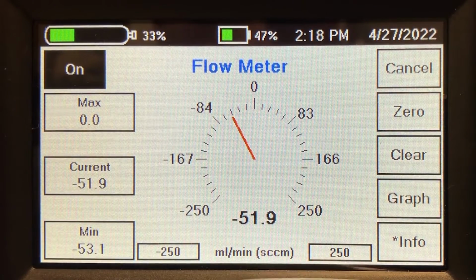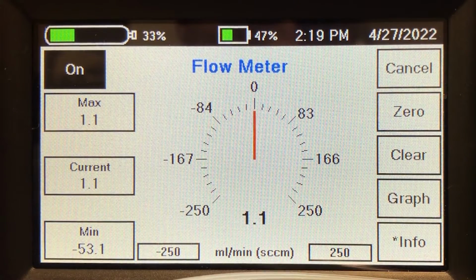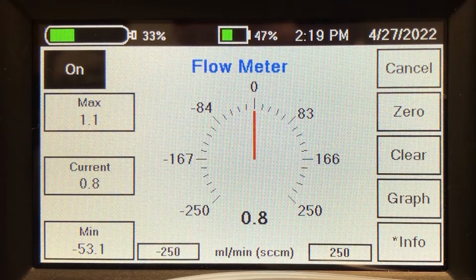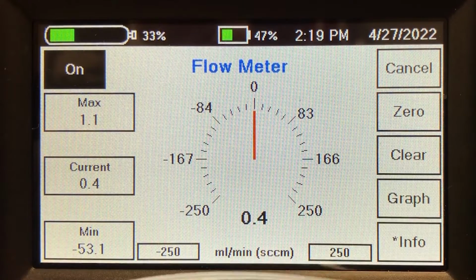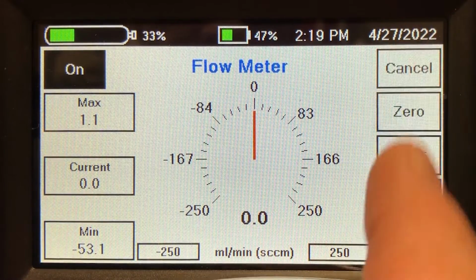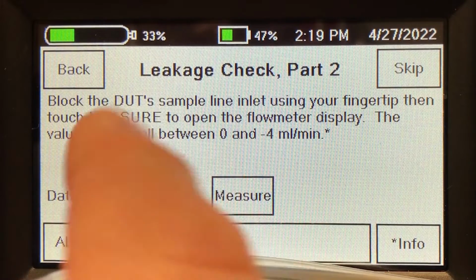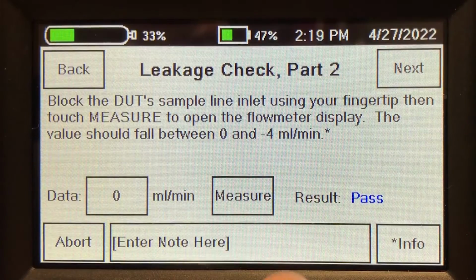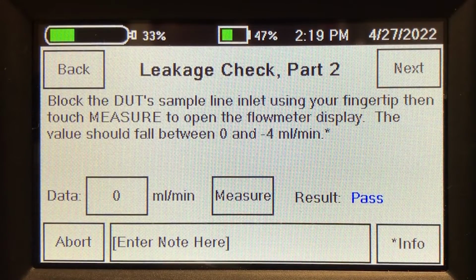I'm going to plug that sample line with my thumb. See, we instantly heard the module basically shut its flow off, and so that shows us there's no leak on that side. See, that's part of the problem with this test.